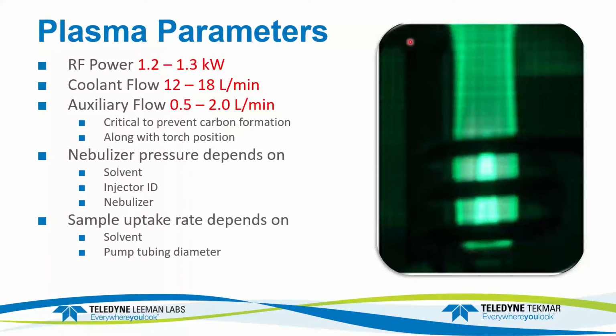The RF power is relatively narrow. We typically don't run more than 1.2 for organics. Occasionally, somebody might run 1.3 and maybe 1.4, but I typically will never run more than 1.2. That seems to be enough. Coolant flow can vary anywhere from the low end of 12 up to a maximum of 18. Again, it depends on the samples and on the solvent that you're using.